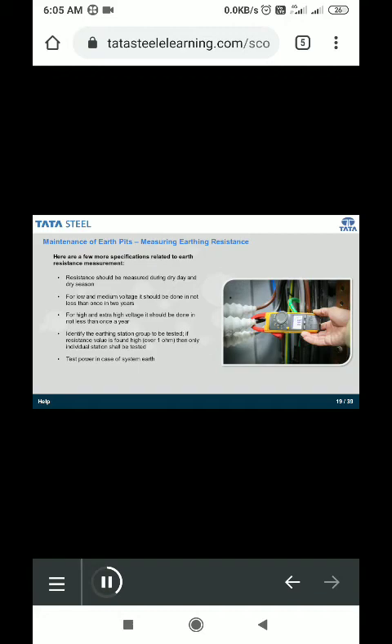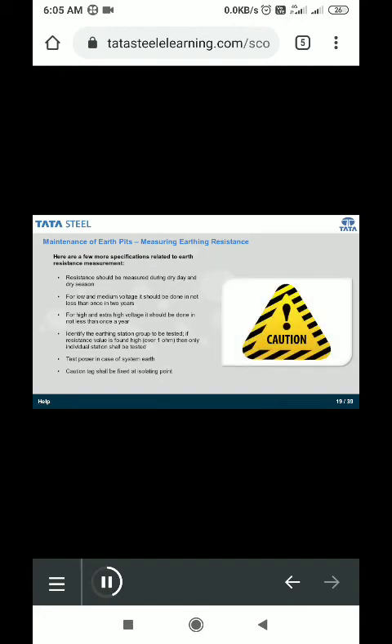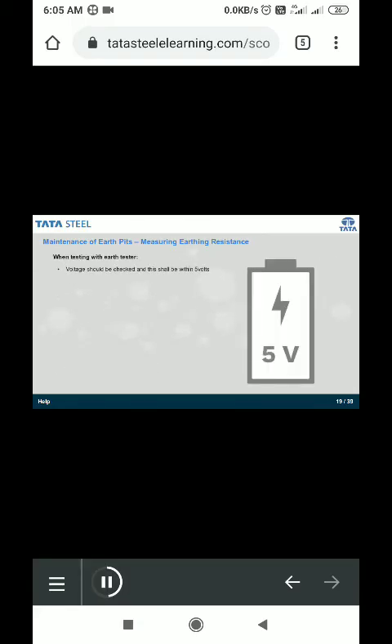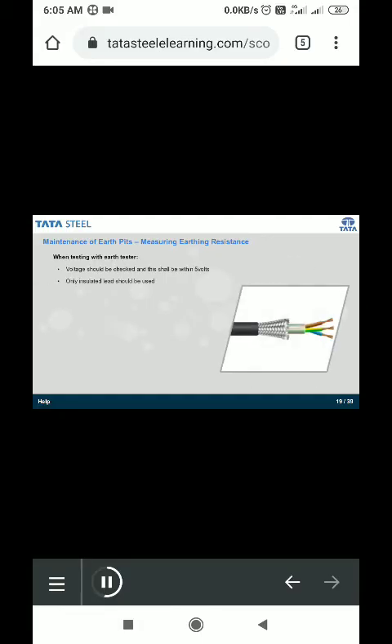Test power in case of system earth. A caution tag shall be fixed at the isolating point. Voltage shall be checked and this shall be within 5 volts. Only insulated lead should be used. The lead should be as short as possible. The current electrode shall be placed at least 30 meters away from the earthing station and the potential electrode midway between them.